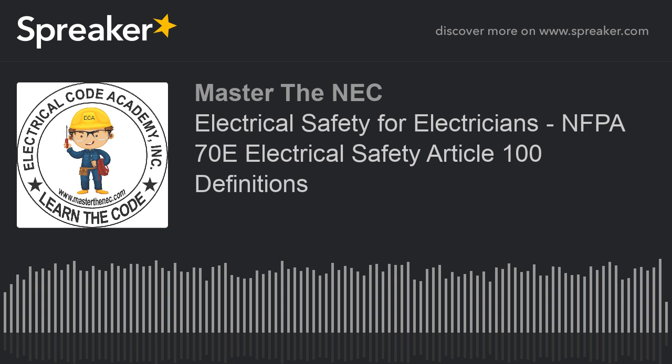Informational note number 1. It says, ARC rated clothing or equipment indicates that it has been tested for exposure to an electric arc. Okay? So obviously ARC rated, arc exposure. It's been rated to a certain level. Flame resistant clothing without an ARC rating has not been tested for exposure to an electric arc. It has only been exposed to flame-resistant ratings, okay? Now, notice that last sentence. It says, all ARC-rated clothing is also flame-retardant. But not all flame-retardant is ARC-rated. Important when you're making that selection.